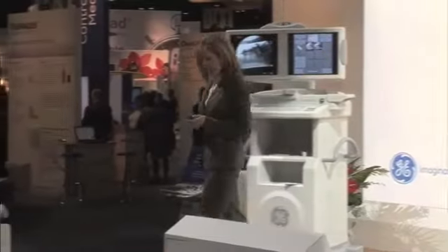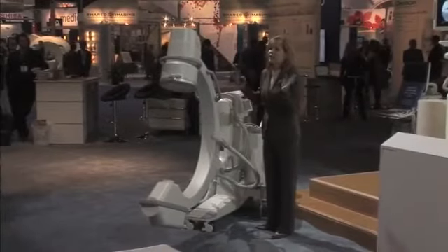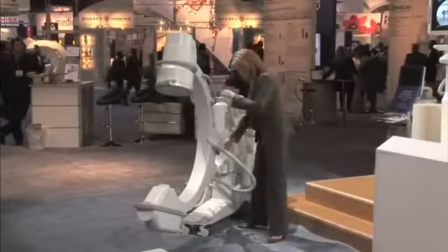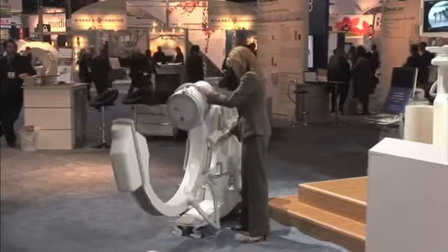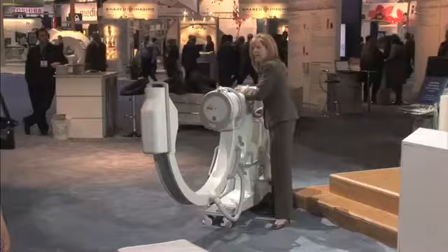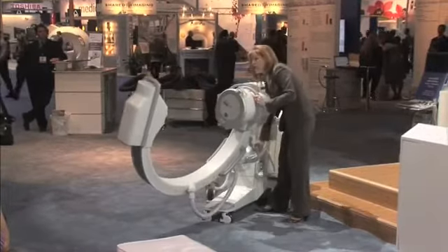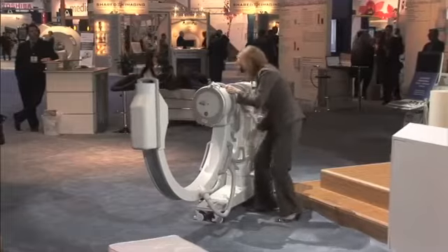Now, we've already seen the positioning challenges the OR can present. Maneuvering a C-arm up to the surgical field when there's staff and equipment in the room can be daunting for techs. Aligning the vertebrae for the perfect spine image or an IM rod for a long bone nailing often means repositioning several times and repeated exposures. With the OEC 9900 SmartView pivot joint, getting additional angles not available on a standard C makes this a snap. So as you can see, with the SmartView pivot joint, positioning is really easy.